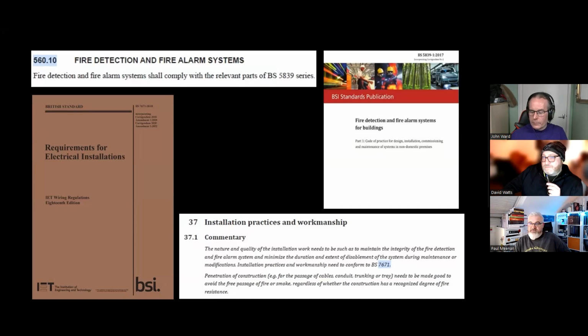Just lastly, while we're on Chapter 56, I know this has got nothing to do with Amendment 2, but for those people in our industry who have said you shouldn't code fire alarms, I call bullshit on that, because 560.10 is very clearly that fire alarms shall comply with BS 5839. You're not expected to know 5839, but if you see it hanging off the wall, you see to it. If you see something that's blatantly wrong with the cabling installation, you code it. Why? Because 5839 requires all the installation practices and workmanship to comply with BS 7671. So if anyone from an industry body says no, you don't code fire alarms, let them stand in a dock and explain that to a judge. Because I can't actually understand the argument against it, other than their inability to support and develop competence amongst electricians.